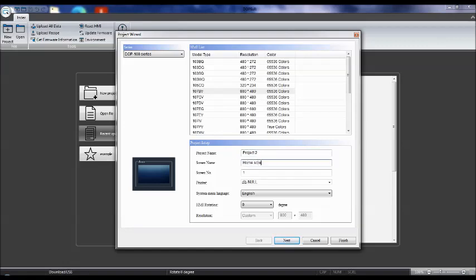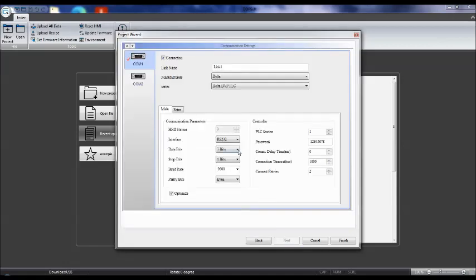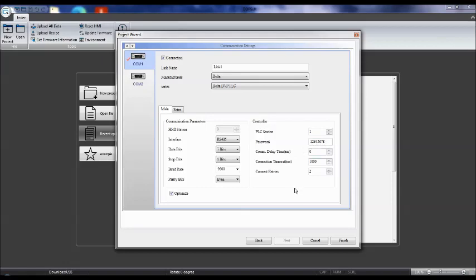Click Next. In the entire certification course, we are using RS-485 communication, and we are using Delta PLC. Set Link 1 to Link 1 and keep all other settings the same, because the same settings are in the PLC also. Baud rate is 9600, data bits are 7 bits — don't change anything. The password would be 12345678, up to 8 digits.